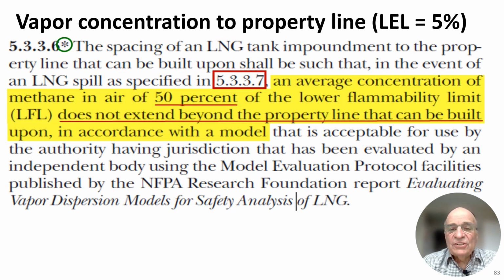When siting an LNG plant, there's also a requirement to meet the code requirements for vapor concentration at the property line. That vapor concentration is given as an average concentration of methane in air of 50% of the low flammability limit that does not extend beyond the property line that can be built upon, in accordance with the models the code lists. And that is for a design spill.